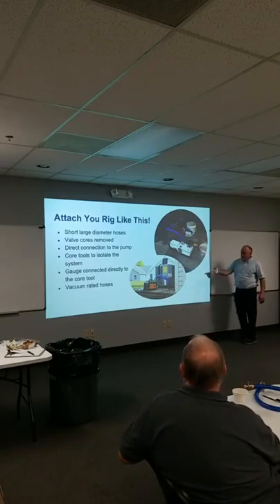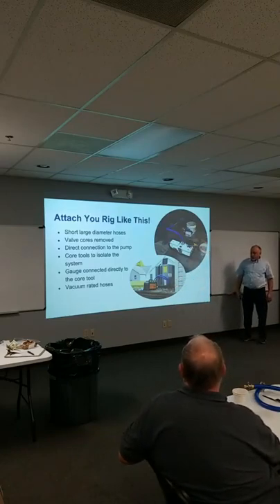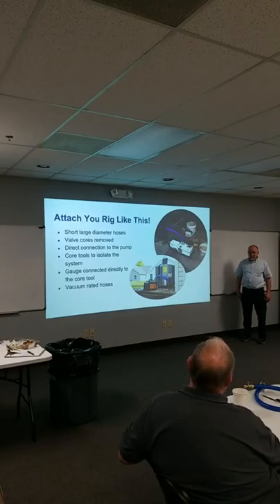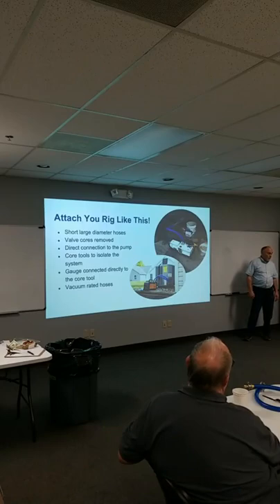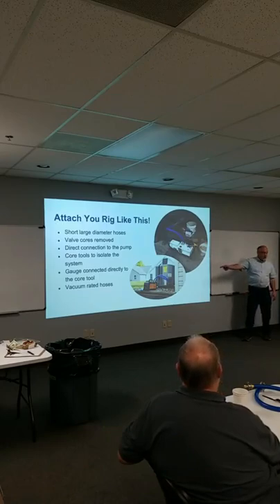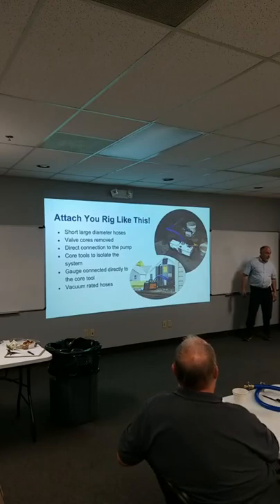Here we're doing 2 hoses. I've found a lot more experience now: 1 hose will do the job just as fast as 2, because the limiting factor is the speed of the connecting tubing. Pulling from both sides of the system is not going to go any faster. So you ask, what about the metering device? It's so short it doesn't make any difference. So today I would always evacuate through the suction line, which has the highest conducting speed, and put the gauge on the liquid line.